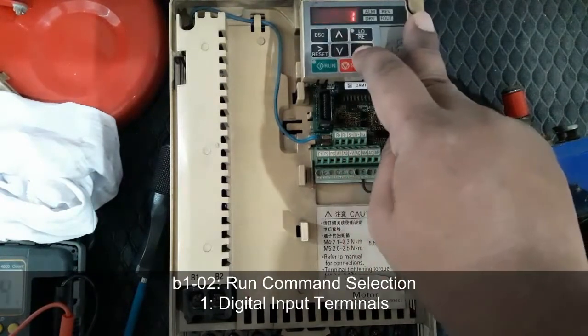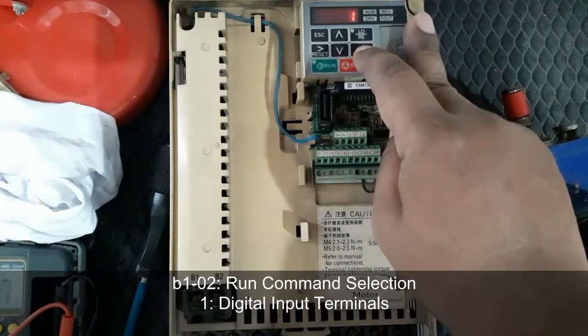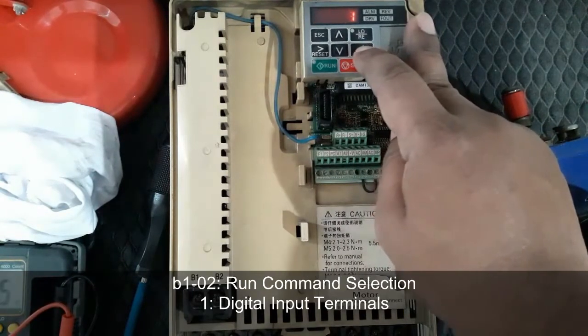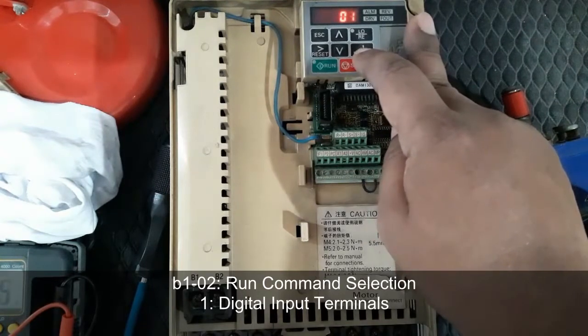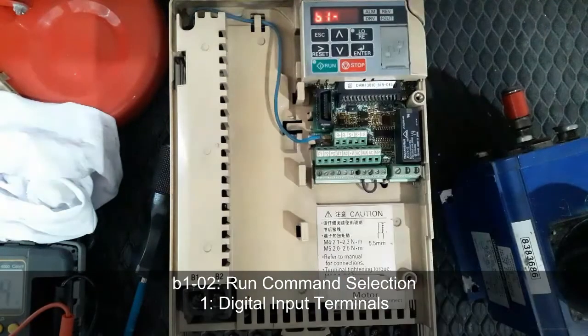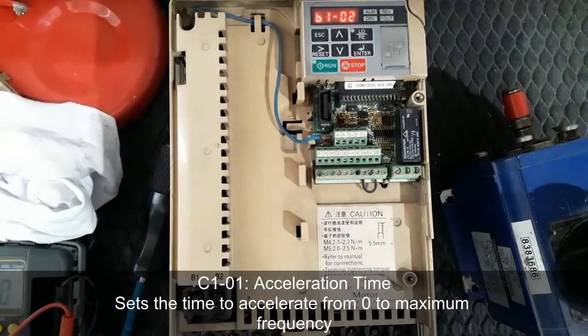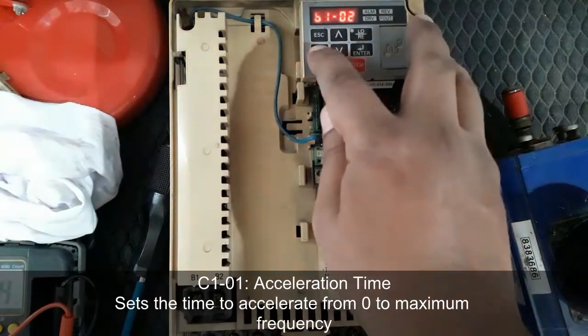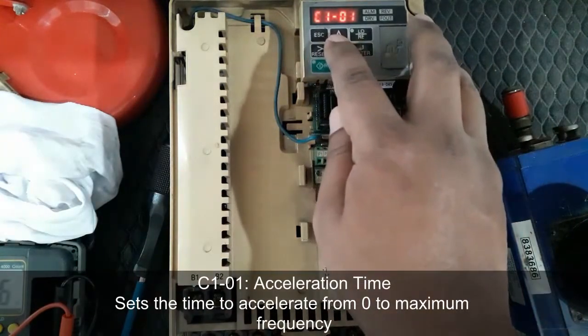Need to set run command selection in parameter B102. Set 1 here for digital input terminals. Press enter for saving the parameter. So here frequency and run command are set for remote operation. That means with the terminal connection we can run by selector switch and speed up by potentiometer.